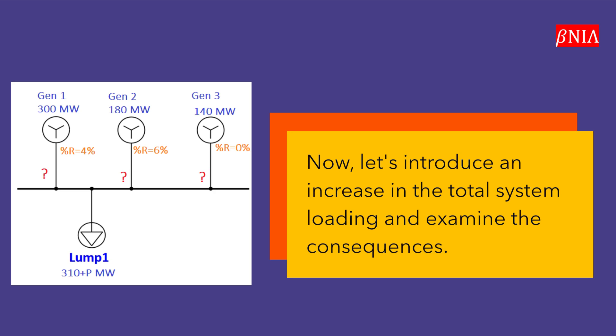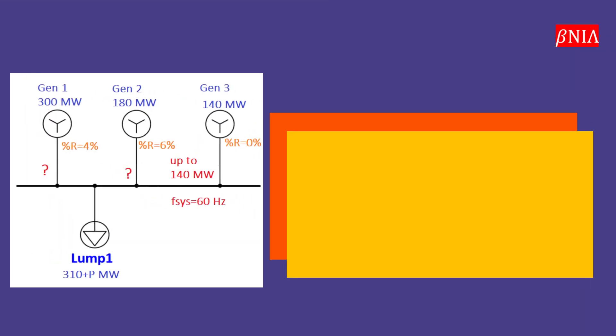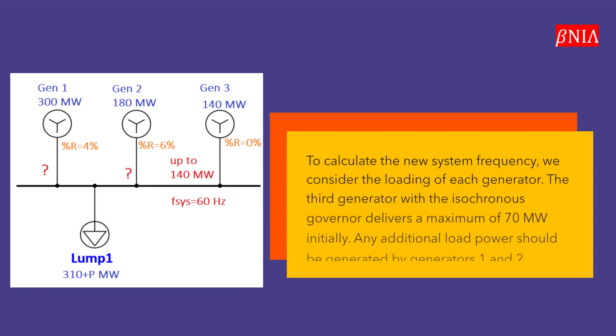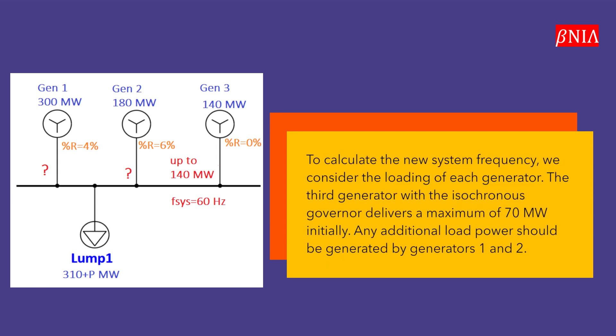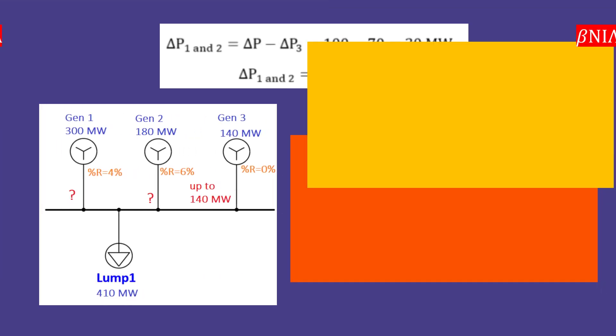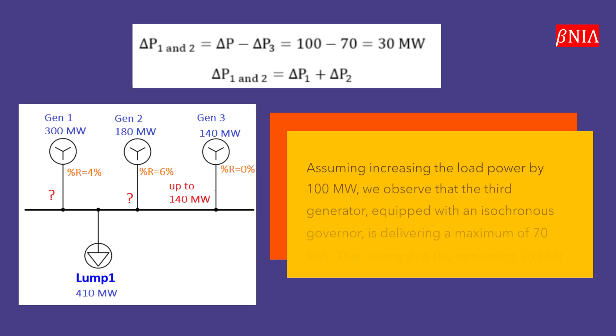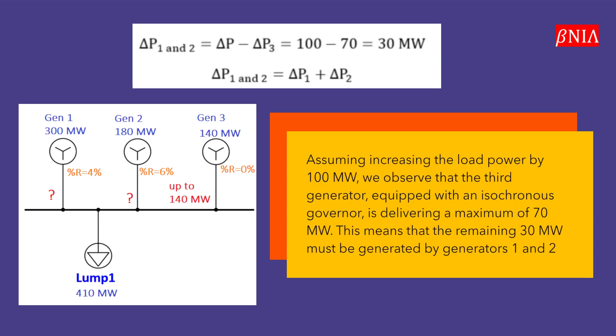Now, let's introduce an increase in the total system loading and examine the consequences. To calculate the new system frequency, we consider the loading of each generator. The third generator with the isochronous governor delivers a maximum of 70 MW initially. Any additional load power should be generated by generators 1 and 2. Assuming an increase in load power of 100 MW, the third generator, equipped with an isochronous governor, is delivering a maximum of 70 MW. This means the remaining 30 MW must be generated by generators 1 and 2.